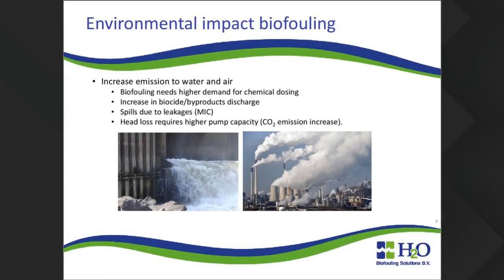Besides operational impact, biofilm also results in an environmental impact. When a fouled system is present, you need more and higher concentrations of chemicals to actually mitigate and prevent further growth of biofouling. So there's a higher demand of chemical dosing. Higher chemical dosing results in a higher discharge of biocides or the byproducts of these biocides, for example, bromoform as a byproduct from hypochlorite.